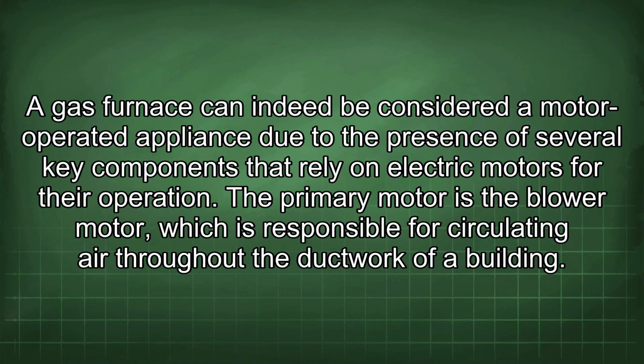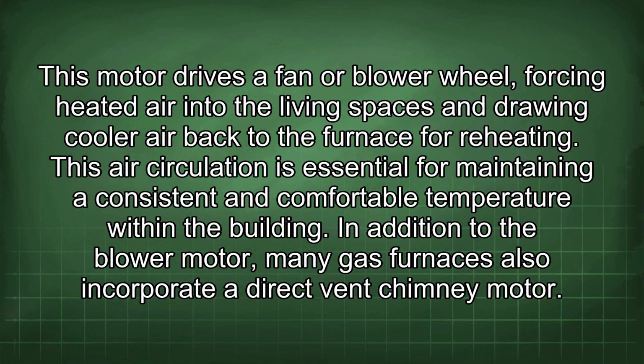A gas furnace can indeed be considered a motor-operated appliance due to the presence of several key components that rely on electric motors for their operation. The primary motor is the blower motor, which is responsible for circulating air throughout the ductwork of a building. This motor drives a fan or blower wheel, forcing heated air into the living spaces and drawing cooler air back to the furnace for reheating. This air circulation is essential for maintaining a consistent and comfortable temperature within the building.